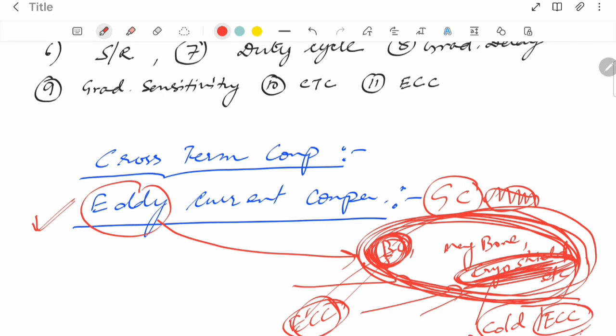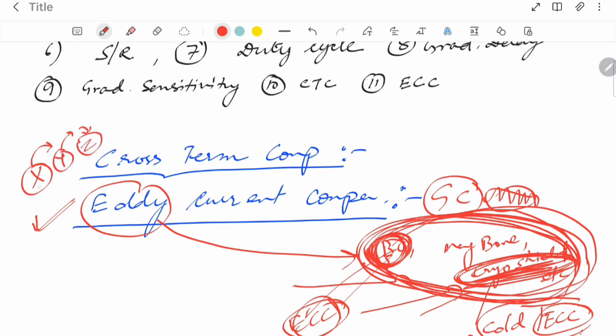Cross-term compensation: when any gradient field is applied on any axis, a small amount of eddy current is also produced on the other axes. For example, if the X axis gradient is on, it creates an effect on the Y axis gradient; if Y is on, it affects Z. We must first determine and measure these cross-axis leakage values and then apply compensation. This is called cross-term compensation.